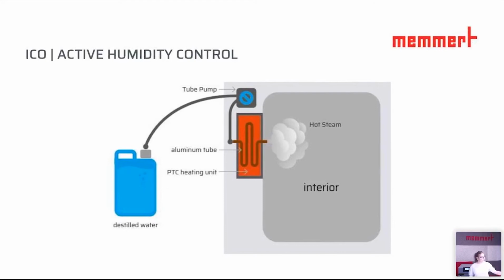All right, in order to visualize this again real quick, we're having a look at the side cut of an ICO. So obviously it all starts with a water tank, which is filled with distilled water. The water is being pumped by a tube pump into an aluminum tube where a PTC heating unit is heating up the water to over 120 degrees Celsius. First of all, to transfer it to steam, of course, and secondly, to also sterilize the water again. The then finished and prepared hot steam is being released into the interior for humidification.